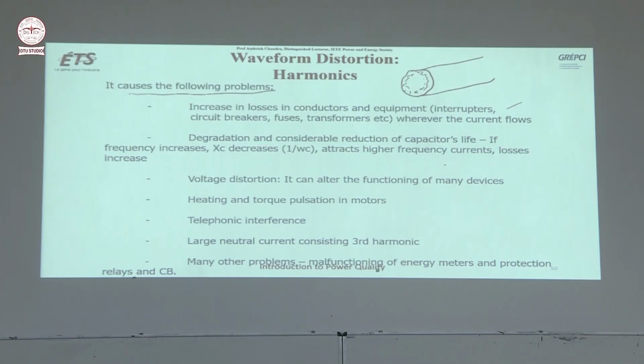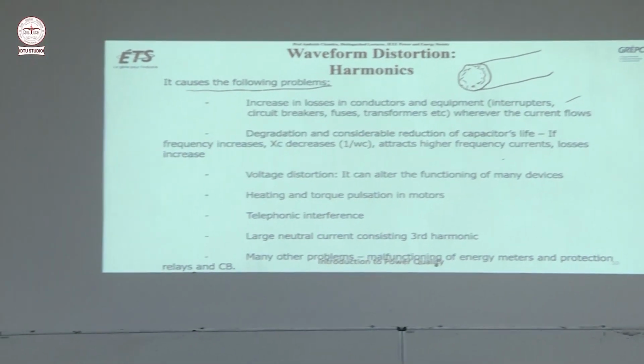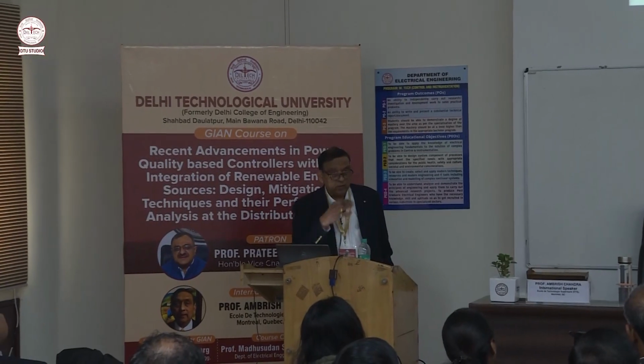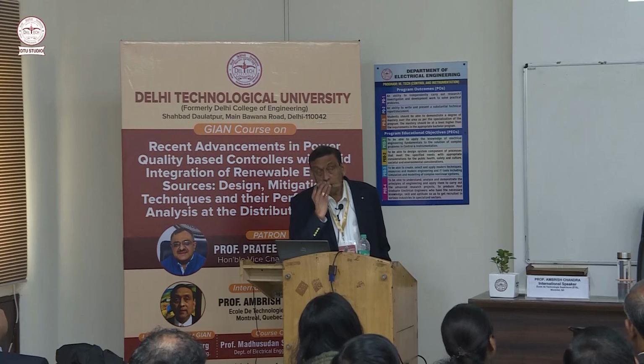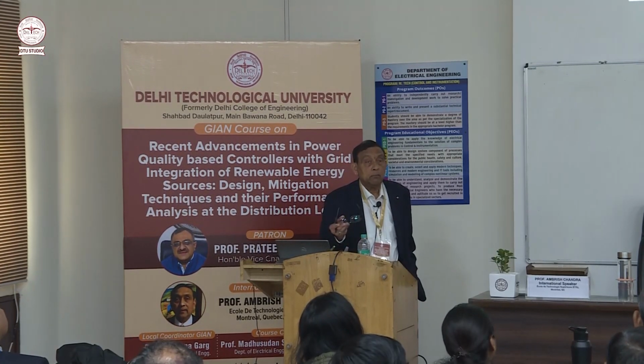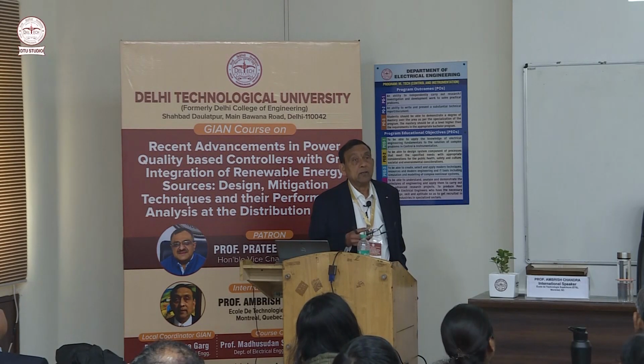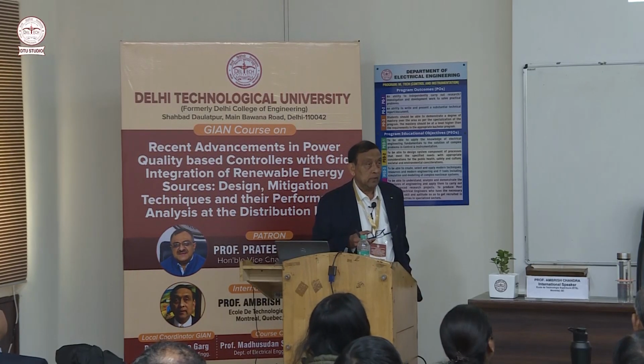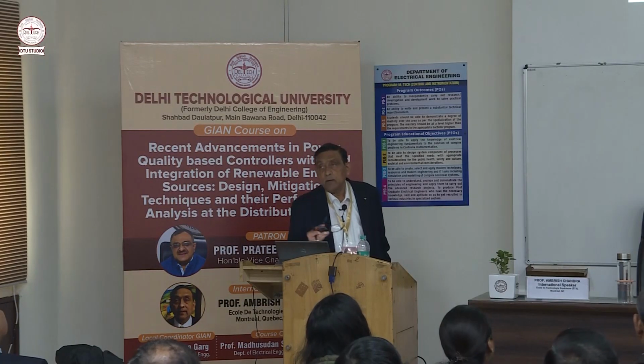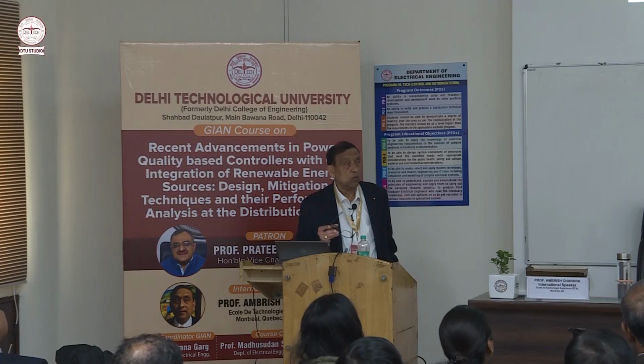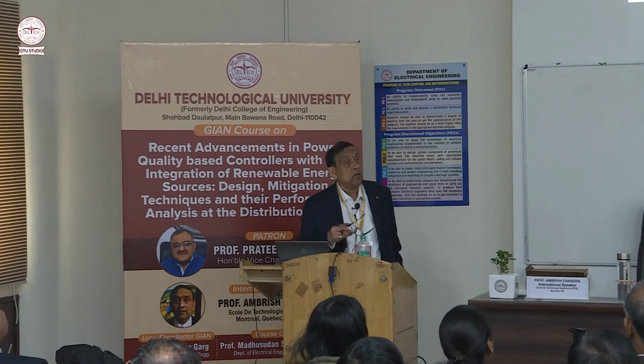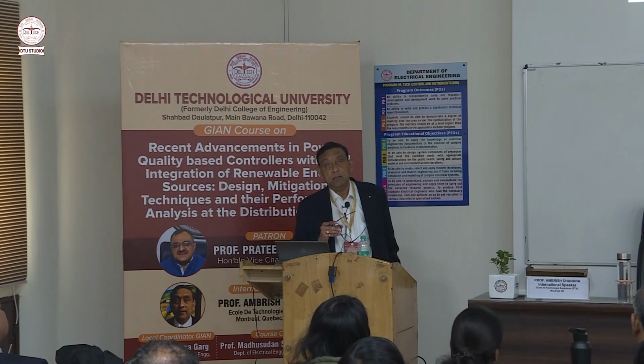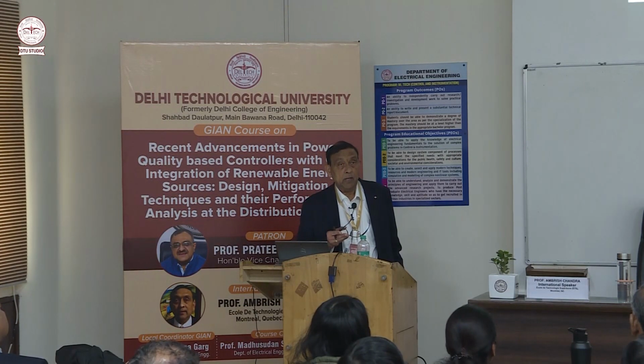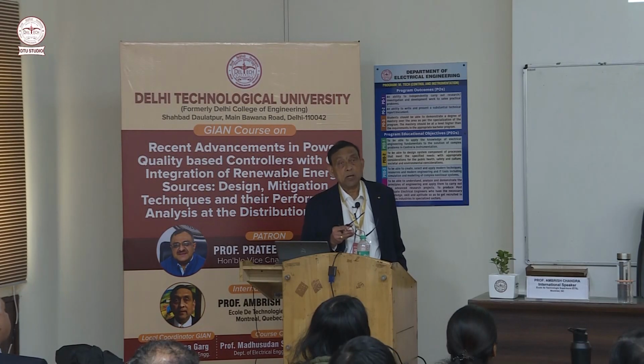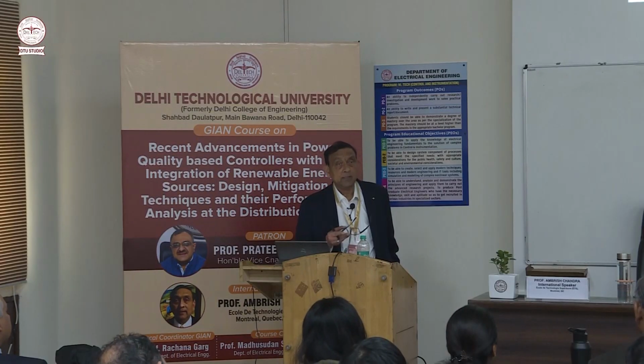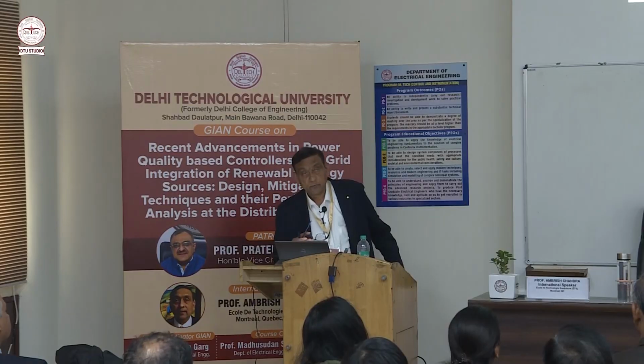But then you have electromagnetic losses also, like hysteresis losses or eddy current losses in the core of the transformer or core of the machines. Hysteresis losses are proportional to the frequency, and eddy current losses are proportional to the square of frequency. Suppose you have fifth harmonic, then hysteresis losses will increase 5 times in the core. But eddy current losses will be 25 times more. This will heat up the transformer, and you cannot load the transformer to the full capacity. You will have to derate the transformer, otherwise the extra losses will decrease its life.